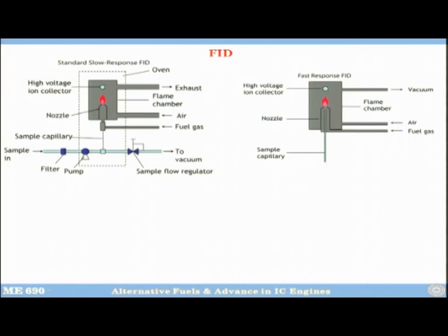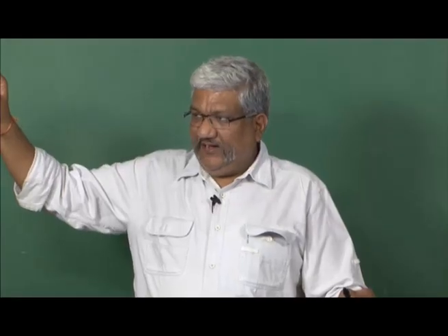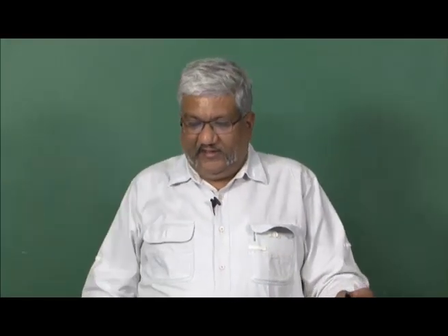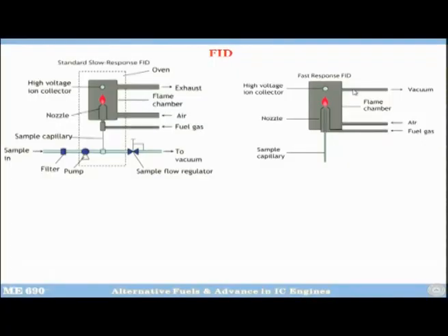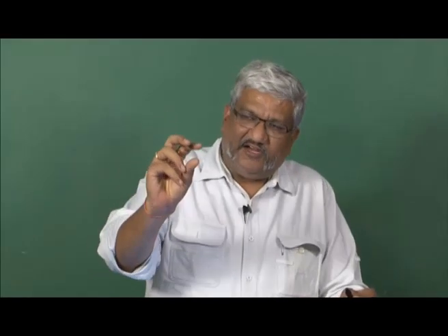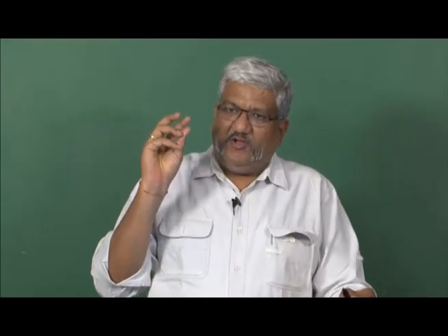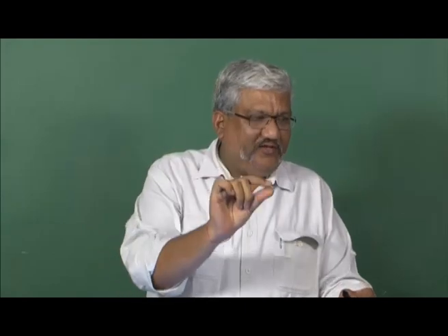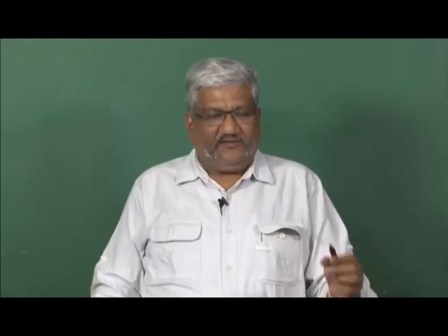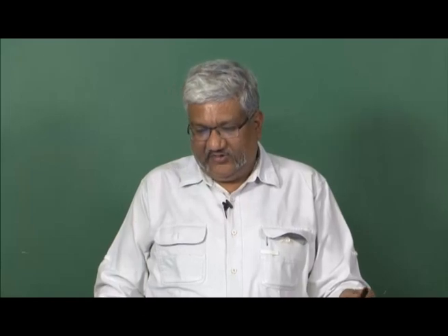So, rather than bringing the sample all the way to the analyzer, what they do is bring this small assembly very close to the sampling point. In fact, they can mount it right outside the exhaust valve of the engine. They just take a very small sample from there, and right there they mount this assembly.